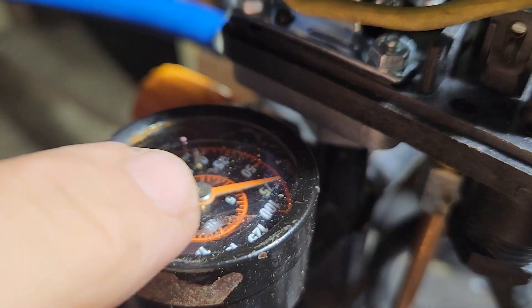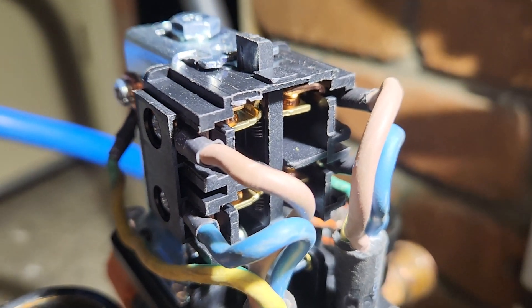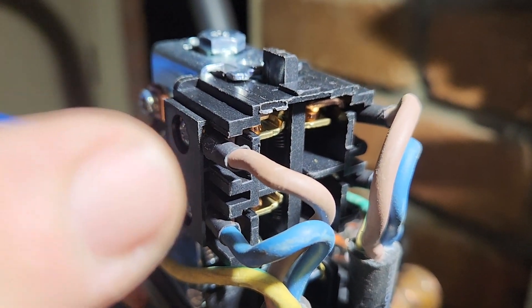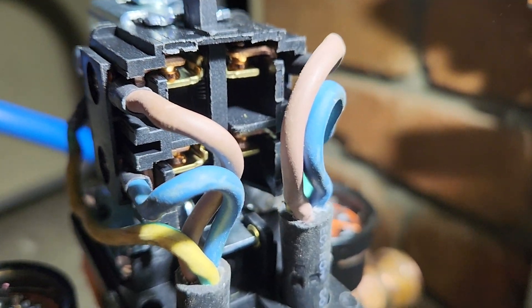So we're going to watch the compressor pump up to about a hundred psi here, and you'll see the diaphragm will get pushed up disconnecting the contacts.